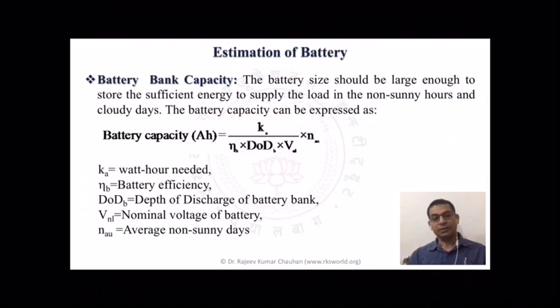What is depth of discharge here? Depth of discharge basically, like I have taken a 150 Ah battery here. If it is mentioned by the manufacturer that the depth of discharge for this battery is 50%, it means we can utilize only 50% of the rated capacity. So out of 150 we can use 150 multiplied by 0.5 equals 75 ampere hours only. That is the meaning of depth of discharge.